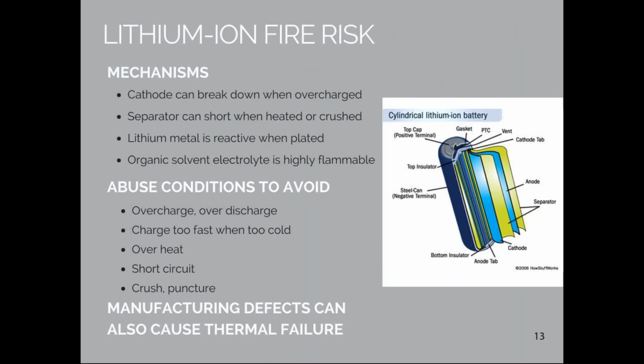To understand the lithium-ion failure mechanisms, we need to look at how the battery is constructed. I'll just draw your attention to a few details in the diagram on the right. We don't need to look at all of it, but on the far right there you'll see several layers, the anode, the cathode, and between them the separator. And please hang in with me, I promise that there won't be a test. Voltage is generated between the electrodes called the cathode and the anode, which is the positive and the negative of the cell. Unlike in a lead-acid battery, these aren't thick, rigid plates. Instead, they're thin films pasted on metal foils, think aluminum foil, and they're separated by a porous plastic film called the separator. Think really, really thin white plastic like a kitchen garbage bag. The separator is wetted with a conductive liquid called the electrolyte, which allows the ions to flow between the positive and the negative.